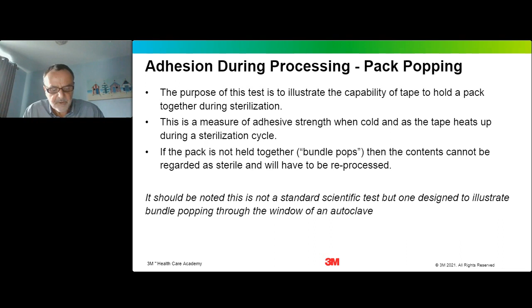A standard pack was prepared, which consisted of two stainless steel bolts, which were wrapped in a textile material and then placed inside a peel pouch, which was then sealed. So it effectively created a sealed space. This was then wrapped in the non-woven material of choice. The idea behind the test was that during steam entry, these stainless steel bolts would create condensate, which would be soaked up by the textile cloth. And being sealed inside a pouch, this creates a sealed volume. So when the pressure inside the sterilizer fell, the condensate would immediately flash into steam, pressurizing the sealed pouch like a balloon, creating an outward force on the tray wrap, which was secured by a small piece of tape.